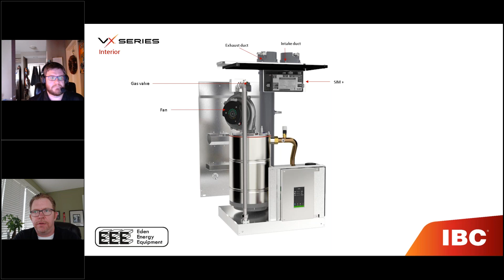This is a custom fan design to IBC. You may have heard about other manufacturers having issues with harmonics and sound with some of the smaller heat exchanger designs, but IBC isn't trying to fit ten other products from other manufacturers into their unit. They have their own ignition control and full control of that combustion motor, which talks back to their own control. That's really the big difference from the standpoint of the fan and its operation.